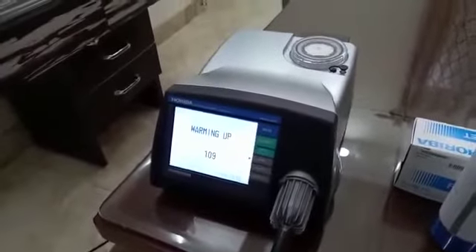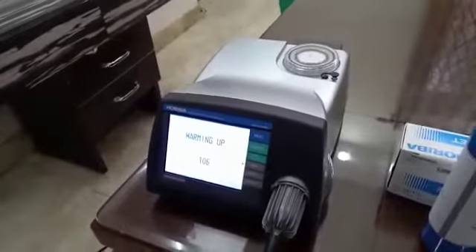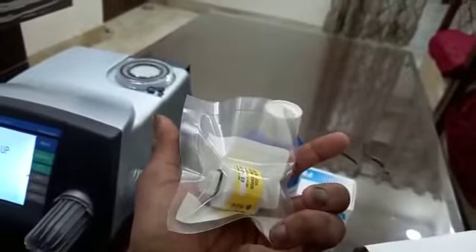In the Mexa, we have this filter, and there's another filter at the back, this one. So the purpose is basically to ensure that the sample that reaches the bench is the purest form of the sample. Along with that, we have this O2 sensor, this galvanic O2 sensor that is used for the measurement. It's new, so I'm not opening it, and I'll tell you the fitment area. It is actually fitted over here. There are two screws, this one and another one is this one. So whenever we open it, there's a section which is used for the purpose.